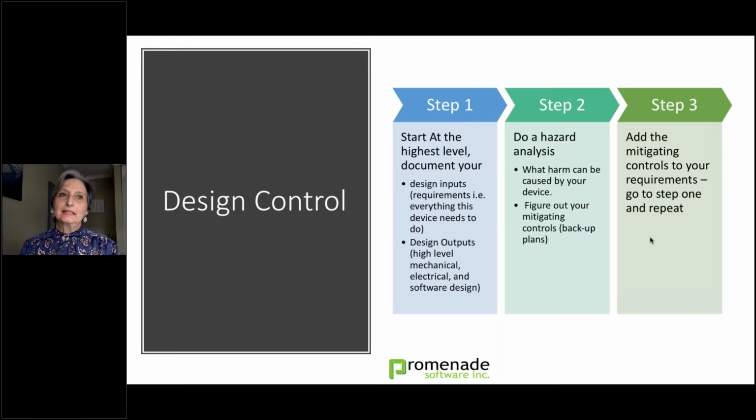The hazard analysis is probably one of the most critical steps when designing a medical device. The reason is that this is a safety critical device. You can actually do harm. So you need to prevent that. You need to understand what kind of harm you can cause and then figure out how to mitigate it with controls.